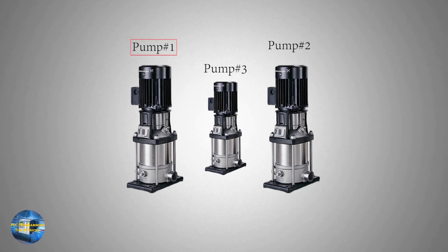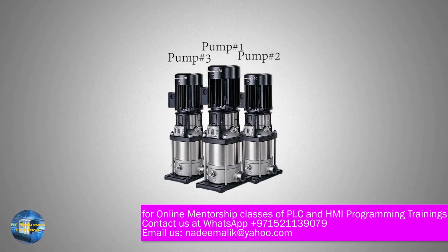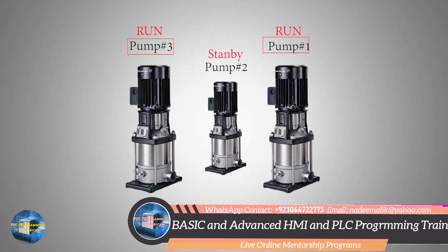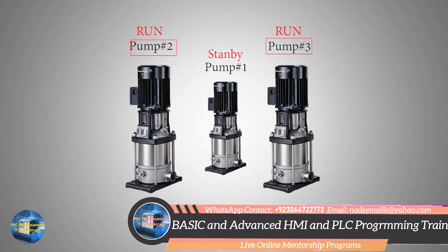Let's suppose we have three pumps: pump number one, pump number two, and pump number three. When we start the pumps, only pump number one and pump number two should turn on, and pump number three should remain standby. In the next cycle, pump number three and pump number one should turn on, and pump number two should remain standby. In the following cycle, pump number two and pump number three should turn on, and pump number one should remain standby.